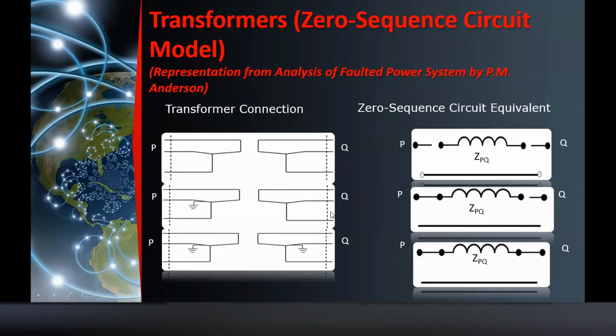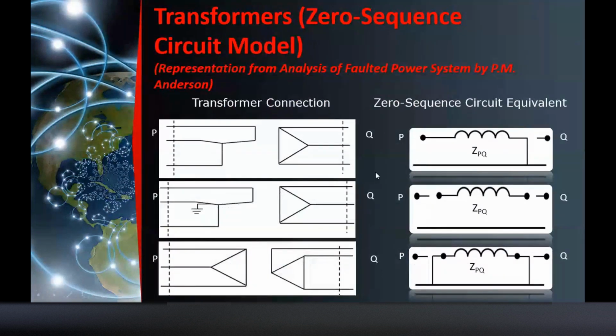Okay, you can see it's open. So definitely, if we're talking about zero sequence, it will not flow to or from the utility. The zero sequence will no longer contribute. For this one, Y grounded, with the secondary ungrounded, it's also open. Okay? When it's Y grounded, that is the one where there is a flow of the zero sequence going back to the utility. Okay? This one is the same.